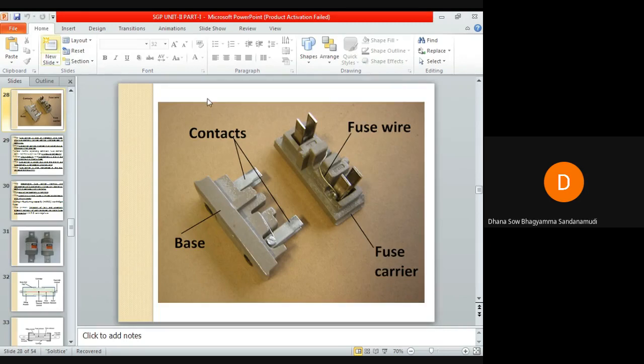So the detachable fuse carrier permits the replacement of the fuse element without any danger of coming in contact with the live parts, and the cost of replacement is negligible. The use of these fuses is limited to domestic loads as well as lighting loads because of low current interrupting capacity, so their usage is limited to only domestic purpose as well as lighting loads.